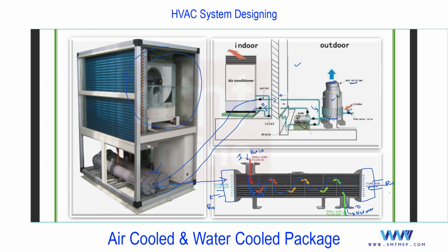So the heat from the water, which is used to cool the condenser, is going to be extracted by using this cooling tower. Only the cold water is allowed to collect at the bottom, and the same water is supplied back to the shell and tube condenser by using this pump. And this pump you can call a condenser pump. Very small capacity pump because it's a package.